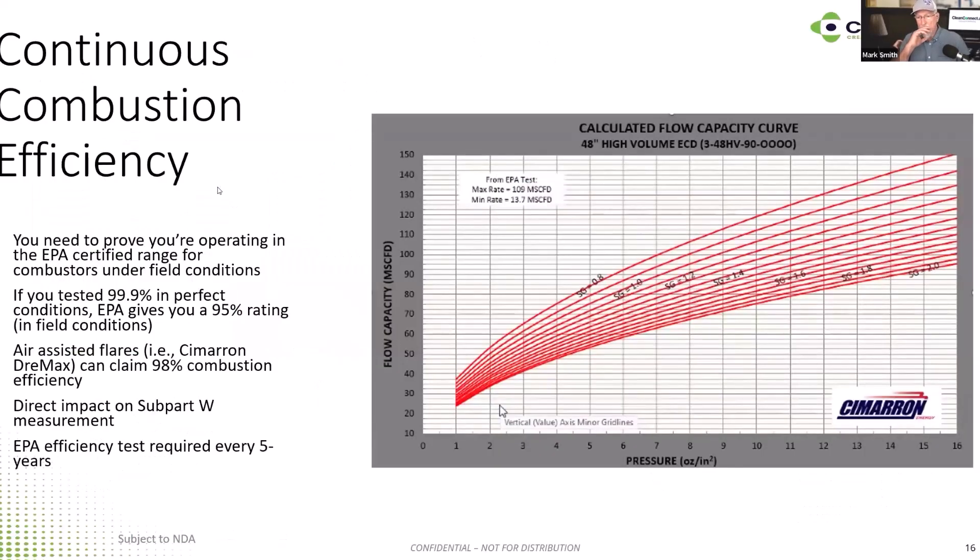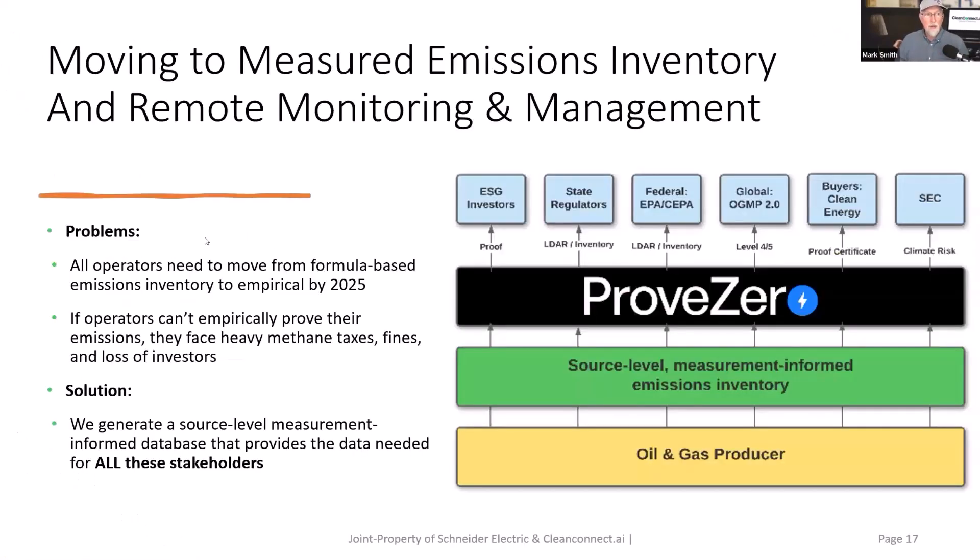On combustion efficiency, operators need to prove they're within compliance continuously. The EPA says they want you to prove 95% compliance, but if you have an air-assisted flare like the Cimarron DreMax, you can claim 98% combustion efficiency. We'll show the difference that makes to operators when you can claim 98% versus 95%. The bottom line from all these different actors is: prove your emissions, show source-level measurement-informed inventory, and demonstrate real-time combustion efficiency through remote management.